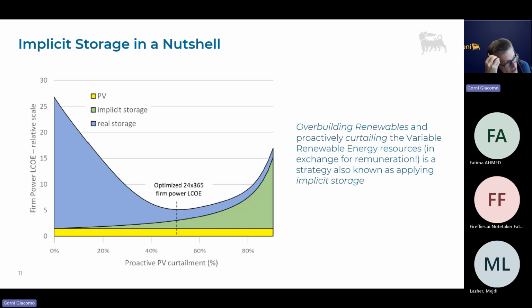You operate under a regime of voluntary self-curtailment, but you receive a premium for that, avoiding the risk of hours in the day when electricity has 0 euros per kilowatt hour cost, where you'd just be losing money. It can be demonstrated that there's a minimum for the system. If you go for full remuneration, that means you're self-curtailing at 90%, which doesn't make a lot of sense because you'd just be wasting your capex investment.